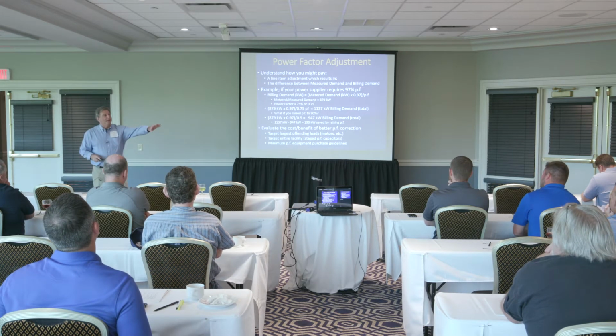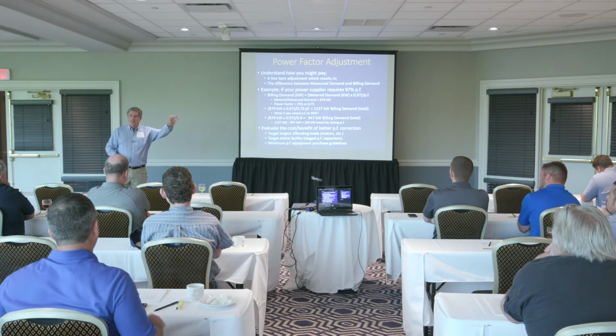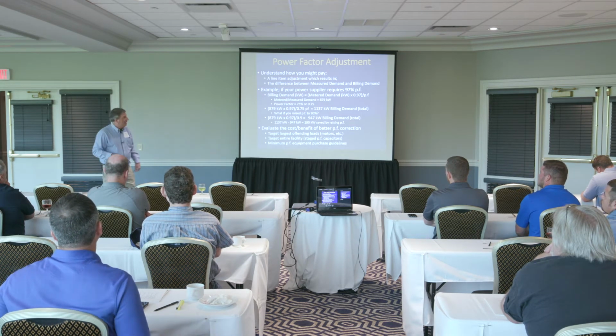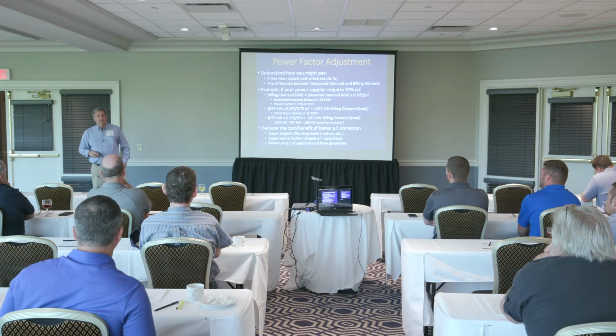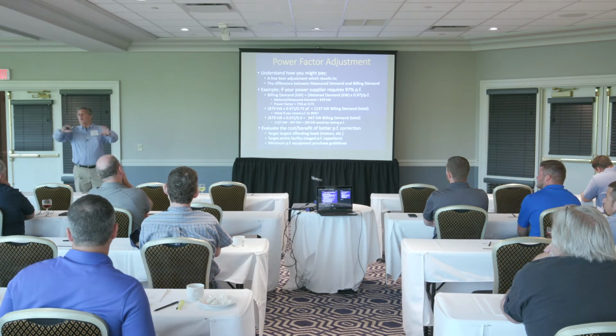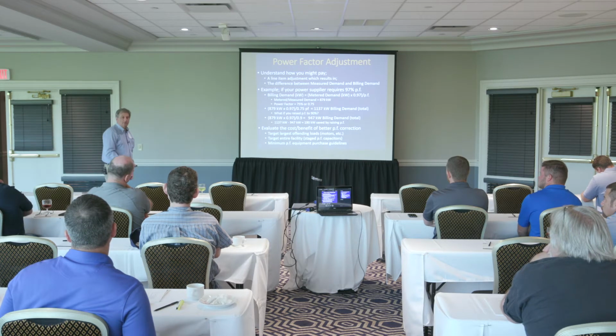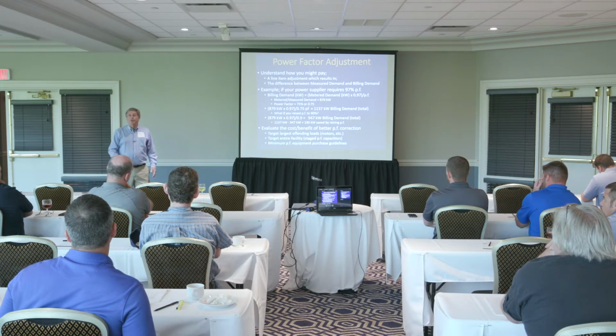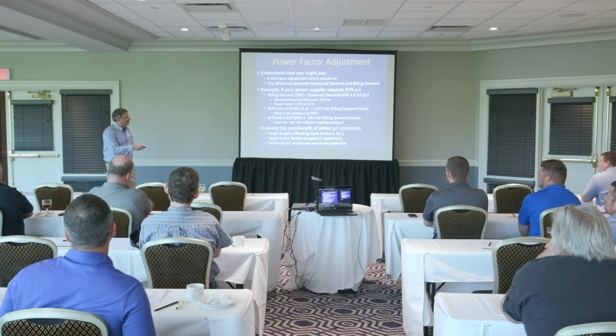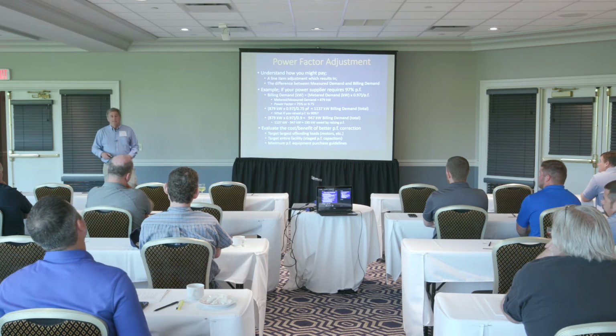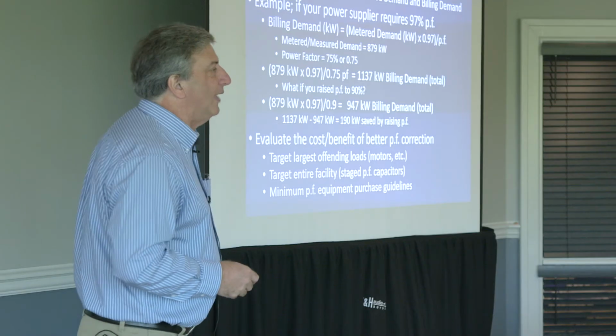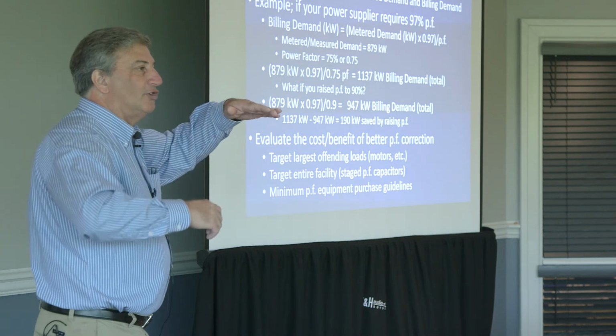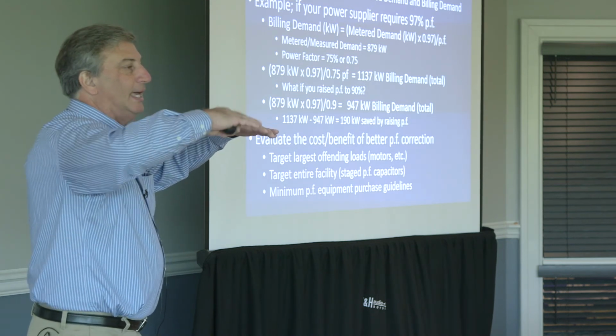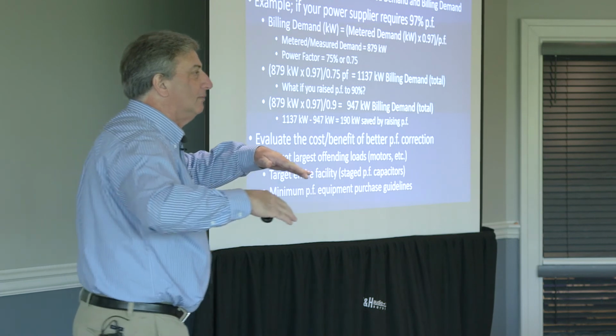If I know it's only 3 or 4 things that drag it down, put the power factor correction at those 3 or 4 things. Now, in many facilities, it's not just 3 or 4 motors, it's a whole combination of lots of different loads. So then I'm not going to put power factor correction on every circuit in my plant. I'm going to go back to the main service and put in a staged power factor correction device where a controller monitors my power factor and kicks capacitors in and out of the circuit as needed to correct. Okay?